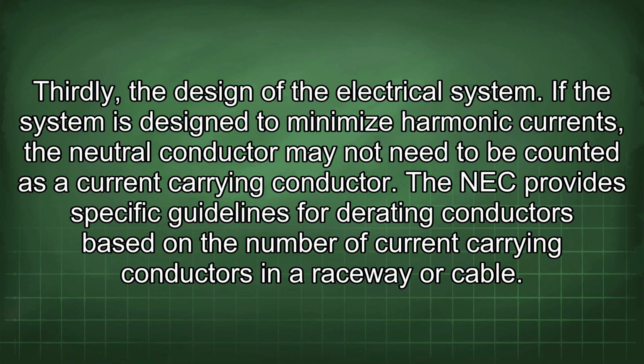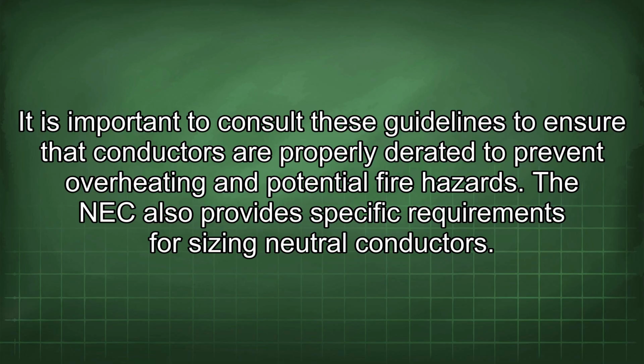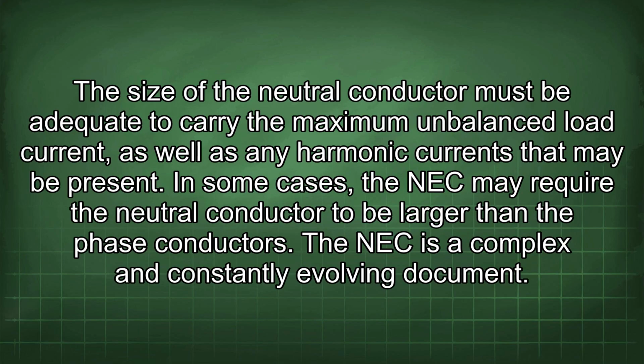The NEC provides specific guidelines for derating conductors based on the number of current-carrying conductors in a raceway or cable. It is important to consult these guidelines to ensure that conductors are properly derated to prevent overheating and potential fire hazards. The NEC also provides specific requirements for sizing neutral conductors. The size of the neutral conductor must be adequate to carry the maximum unbalanced load current, as well as any harmonic currents that may be present. In some cases, the NEC may require the neutral conductor to be larger than the phase conductors.